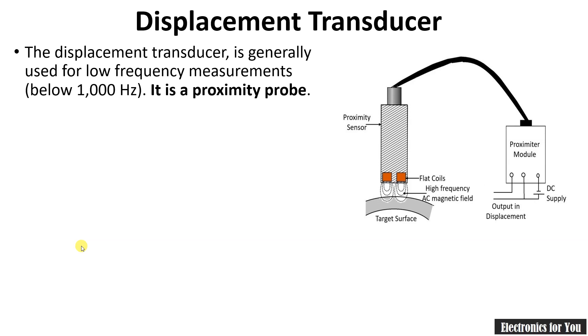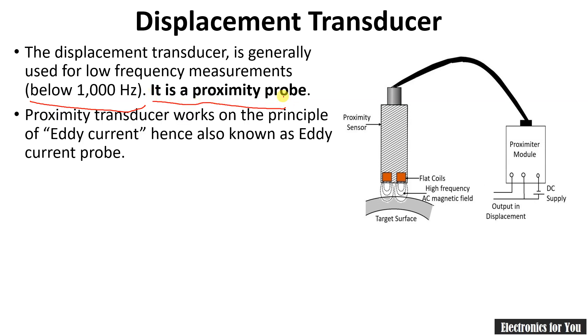As stated in part 1 of this video, the displacement transducer is generally used for frequency components below 1000 hertz and is therefore used for the lower frequency range, up to 1000 hertz. This type of transducer is also known as a proximity probe. The proximity transducer works on the principle of eddy current, hence it is also known as an eddy current probe.